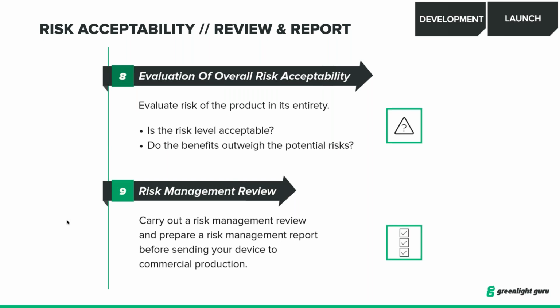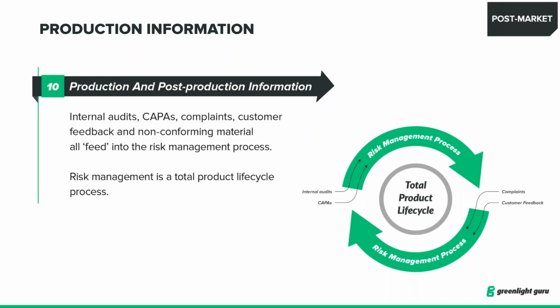But it is an expectation that you are documenting your risk acceptability criteria. It is an expectation that you have had some review of that information within your risk management file. It is an expectation that key executives at your company are involved in that process. And that's all I'll say about that for right now.